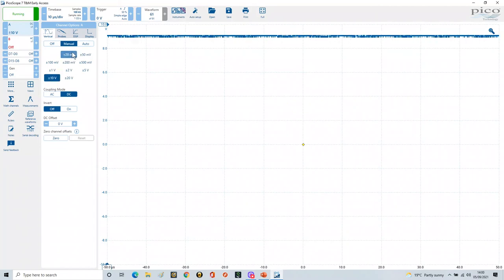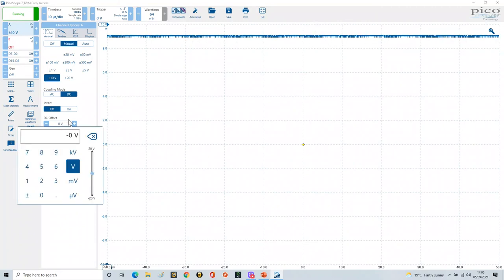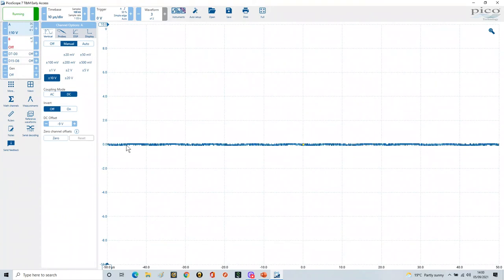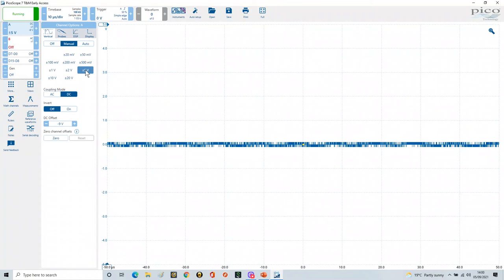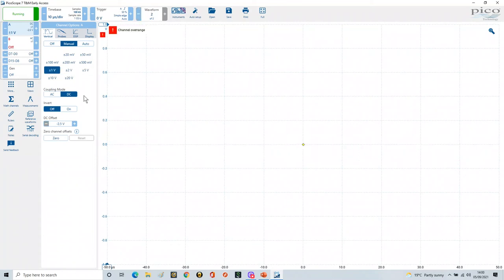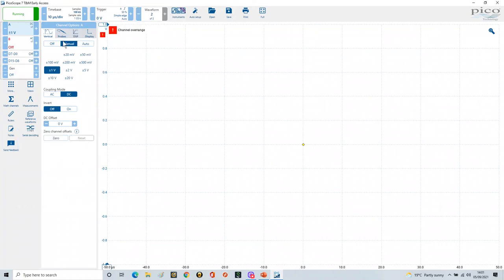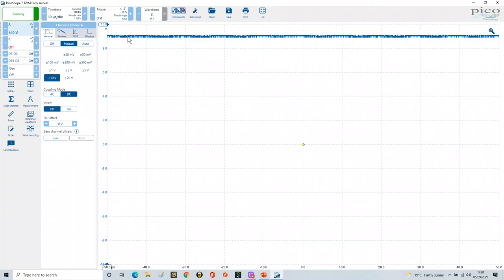If I try to move in to see this, I could add a minus nine volt offset and let's just see what happens. You can start to see something, but I've got this plus 10 volts range. Can I see this in any more detail? Going to plus two — now it's gone over range and we've lost the signal. We're not really able to see the signal anymore because as we've changed the scaling, the DC offset has changed as well. So let me get this back to zero offset and go back to plus or minus 10. There we are with the signal back. We can't see this tiny signal that's sitting on this DC level.